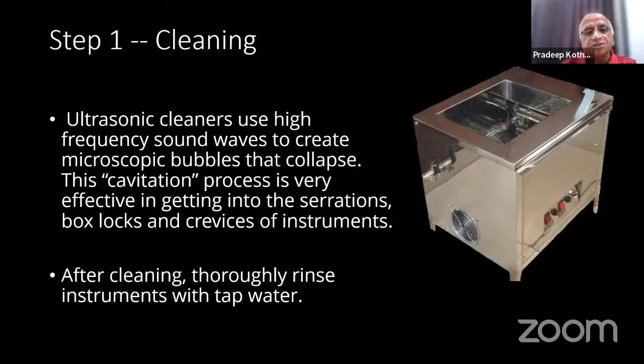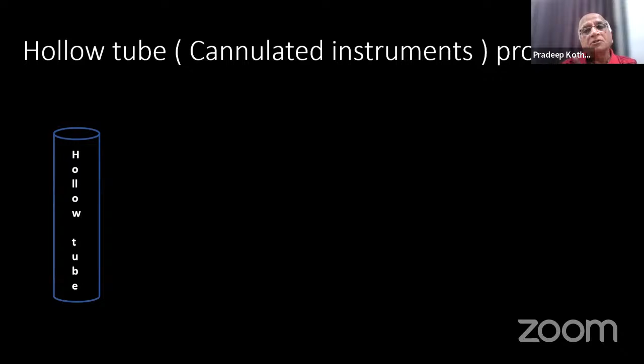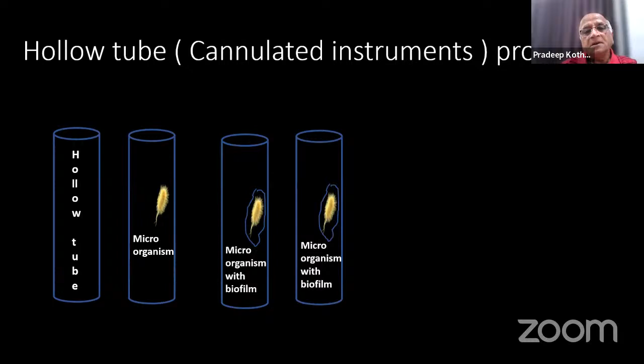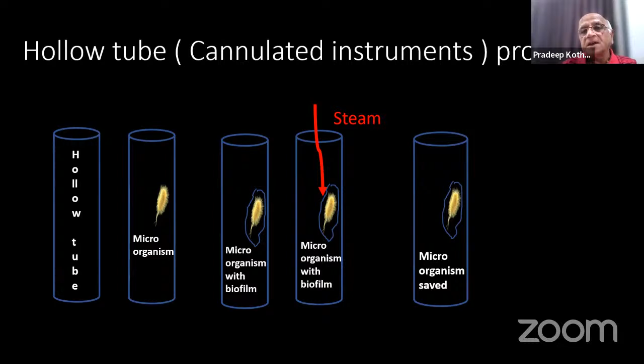Even after this, you have to rinse the instruments in tap water and keep them for drying. Hollow tubes are a problem. There are many instruments of ours in orthopedics that are cannulated. The hollow tube instruments are a problem, and you have to clean them properly. Some microorganisms are seen inside the hollow tubes, sometimes with biofilms. Even though the steam comes, the biofilm will not be destroyed by the steam, and the microorganisms are saved, so your instruments will not be properly autoclaved or sterilized. So how do you do it?